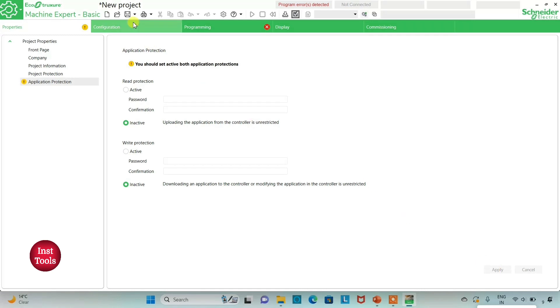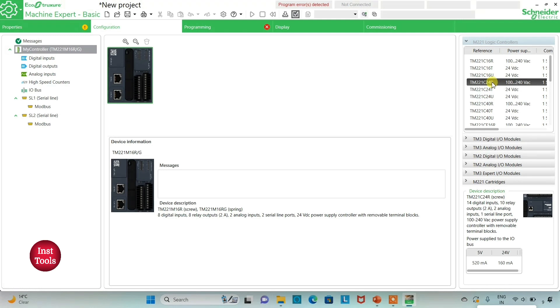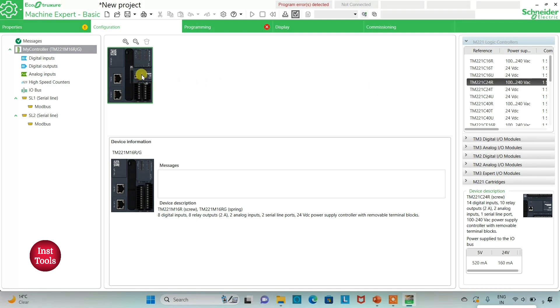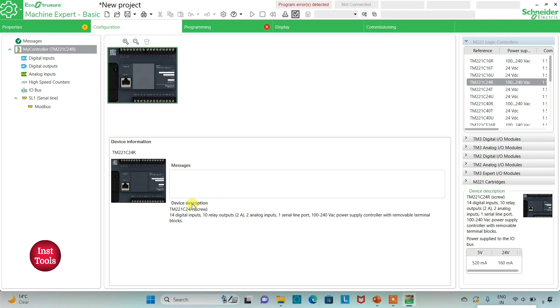After that I will go to the Configuration tab where we have to select and configure the logic controller. Here is a list of different logic controllers. I will be using TM-221-C24R. I will click on it and drag it in. This device has 14 digital inputs, 10 relay outputs, 2 analog inputs, 1 serial line port, and a 100-240V AC power supply controller with removable terminal blocks.